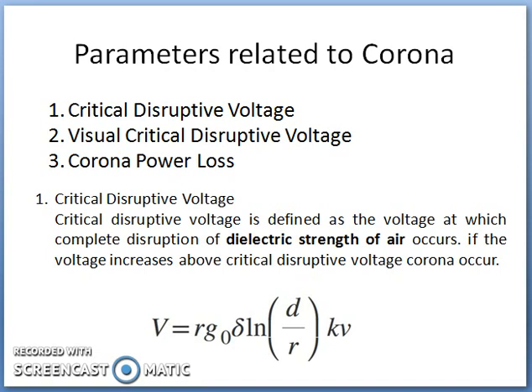If the ratio of spacing between the conductors to the radius of the conductors is less than 15, then flashover takes place before corona occurs. But in practice, this ratio is very, very high and there is no possibility of flashover.